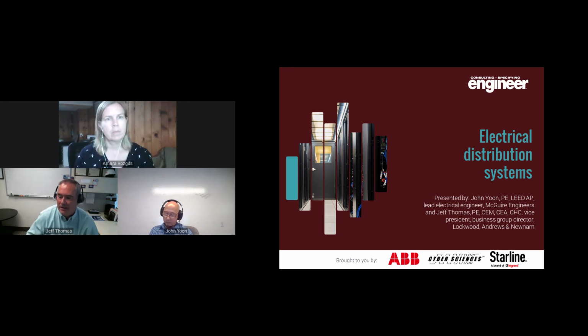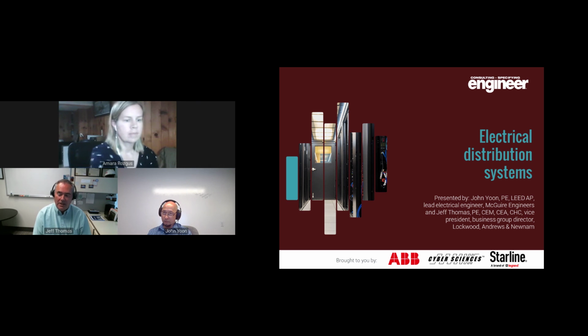Sure. So I'll even go so far as to talk about low voltage. Low voltage is anything up to 600 volts. So typically, most of us are going to operate in the low voltage range with our 480, 240, 208, 120. Medium voltage, depending on who you ask, is either 1,000 to 35,000 volts or 2,400 to 69,000 volts. And then high voltage is anything above that. Typically, we are going to operate at medium voltage in the 4160 or the 5 kV range, or the 12,470 or 13,000, which is the 15 kV range.